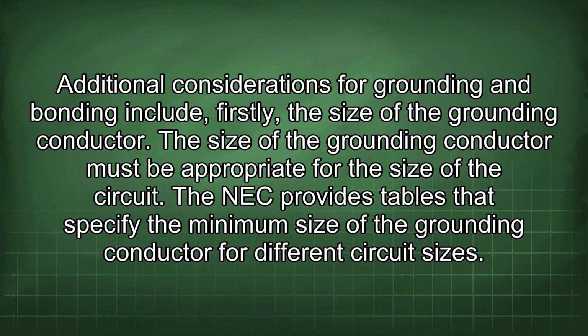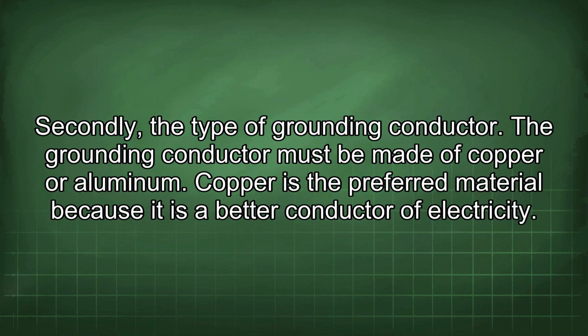Additional considerations for grounding and bonding include: firstly, the size of the grounding conductor. The size of the grounding conductor must be appropriate for the size of the circuit. The NEC provides tables that specify the minimum size of the grounding conductor for different circuit sizes. Secondly, the type of grounding conductor. The grounding conductor must be made of copper or aluminum. Copper is the preferred material because it is a better conductor of electricity.